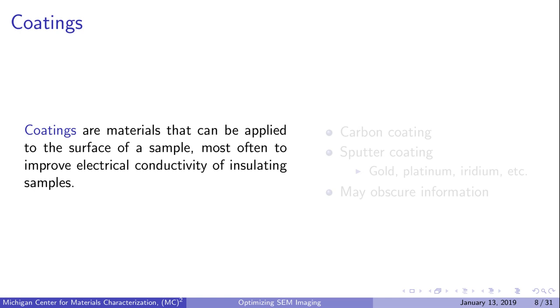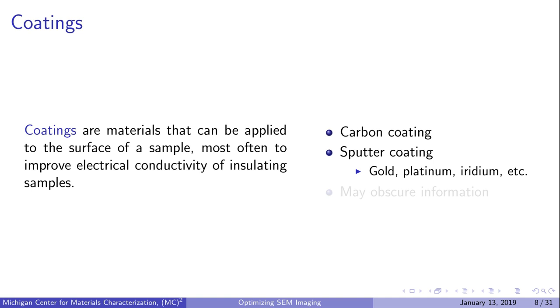Coatings are materials that you can apply to the sample surface, most often used to improve electrical conductivity of insulating samples and avoid charging. Various coatings can be applied using the carbon coater or sputter coater at MC Squared, the most common being gold. While coating insulating samples is often necessary, coatings cover the surface and may obscure information depending on the coating composition and thickness. This is important if your features of interest are near the surface or if you plan on using EDS for element identification, as you may pick up signal from your coating. It's generally recommended that you try imaging a sample before coating it.